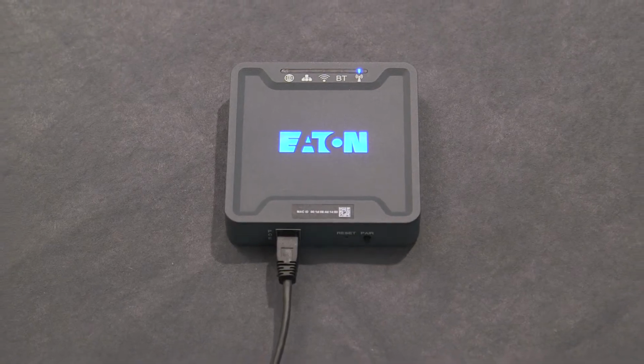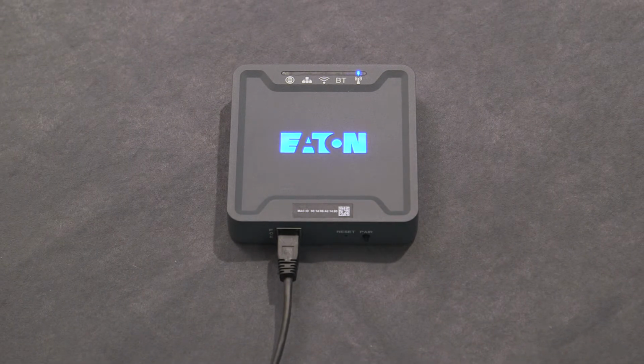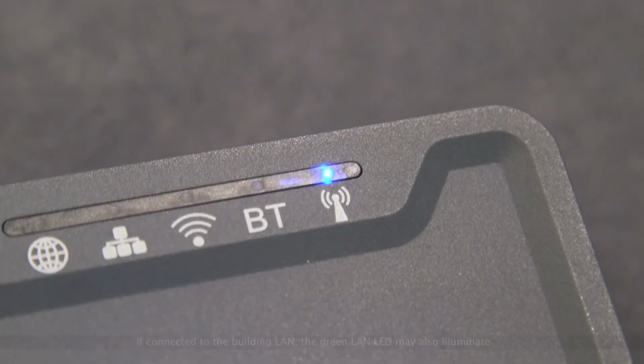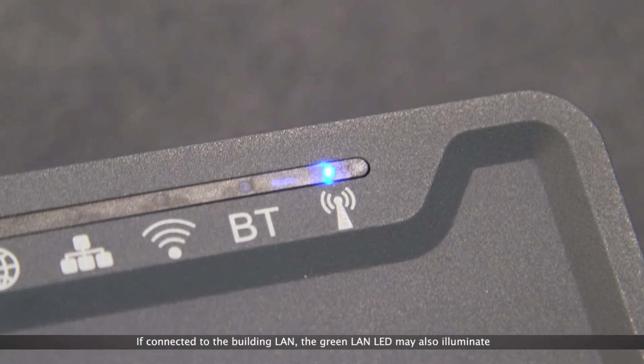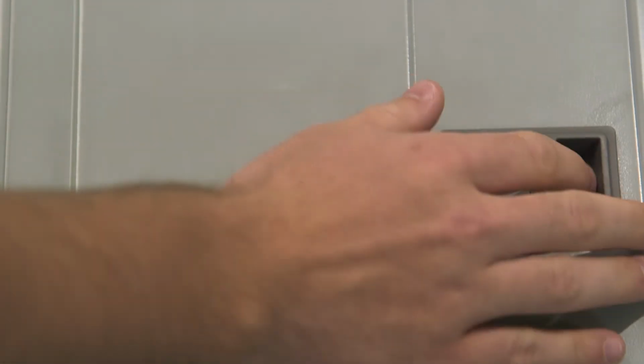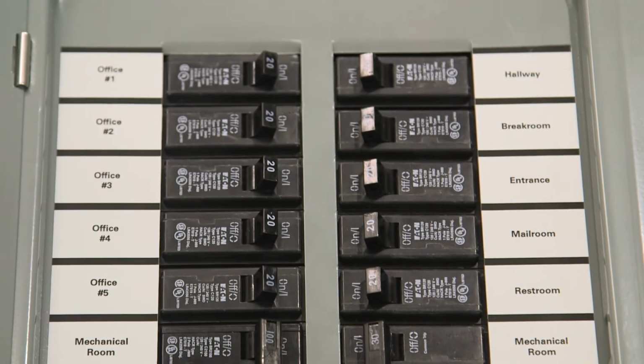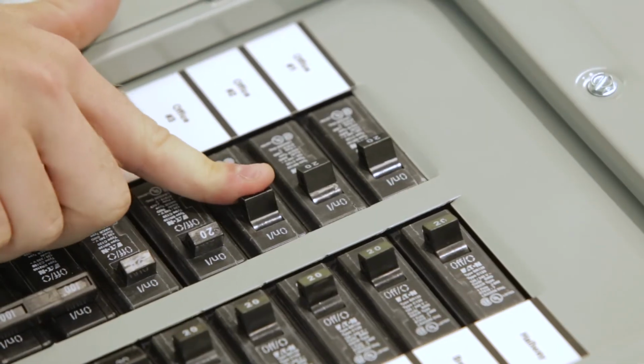Confirm that the wireless area controller's Eaton logo LED is illuminated. Verify that the blue 802.15.4 LED on the rear panel is on. Next, make sure that power is applied to the circuits connected to the WaveLinx devices.